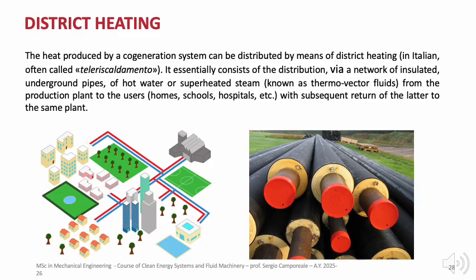A common real-world application is found in northern regions with long and cold winter seasons, such as northern Europe or northern Italy, where district heating networks serve entire cities or large university campuses. In these systems, supply water temperatures are typically in the range of 80 to 120 degrees Celsius, with return temperatures between 40 and 60 degrees Celsius, and network lengths that can extend over tens of kilometers. A single cogeneration plant can supply thermal power on the order of tens to hundreds of megawatts, significantly reducing the need for individual boilers and improving overall energy efficiency. After heat is delivered at the user substations, the fluid is returned to the same plant, forming a closed-loop system.